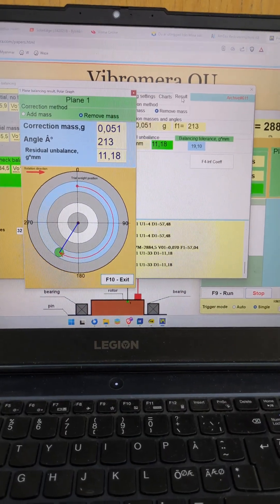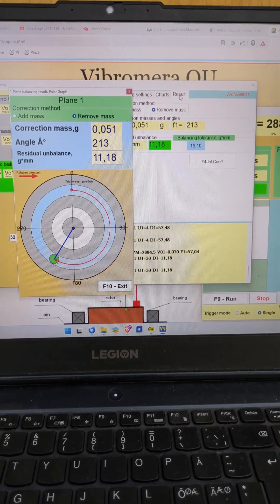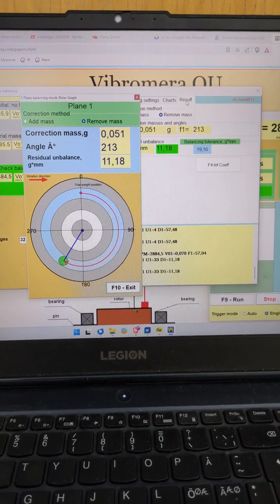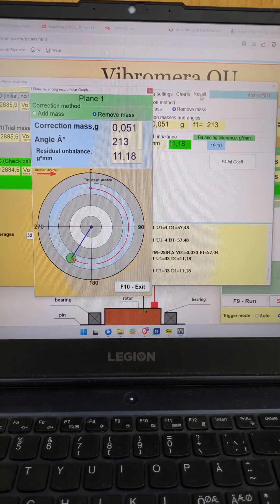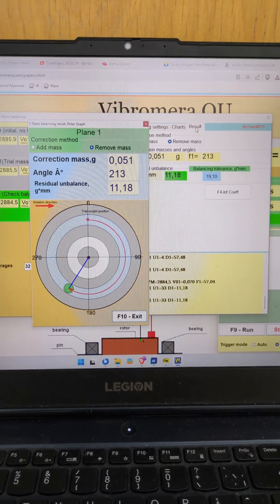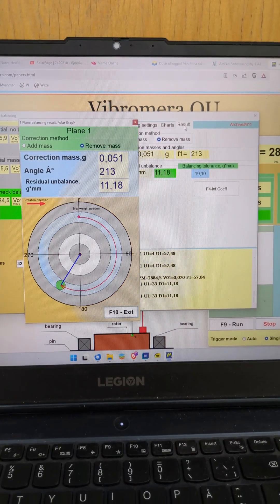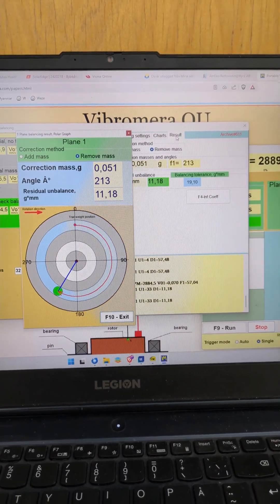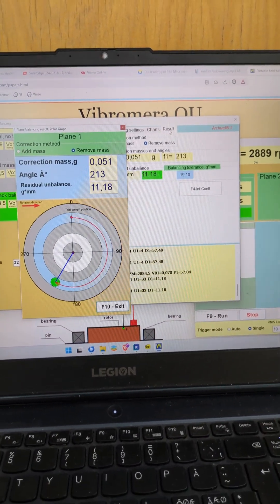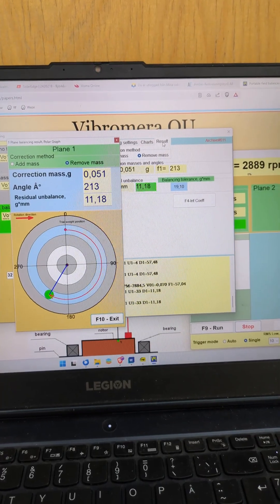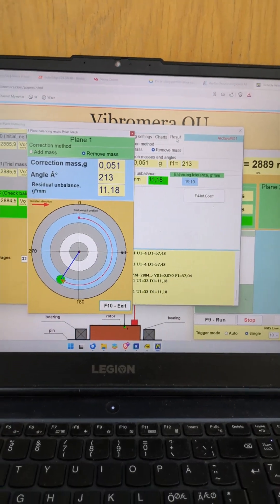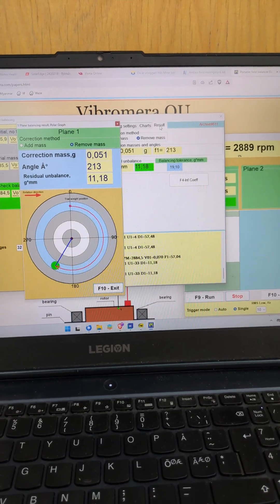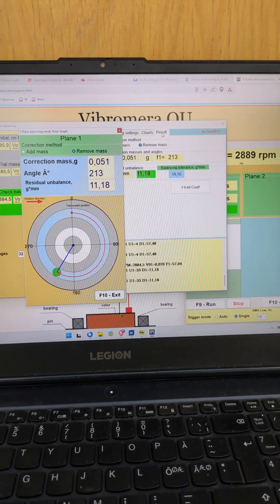Voila! We are now within G1 for a 7 kilo 3500 rpm centrifugal fan. It's fantastic and it runs super smooth.